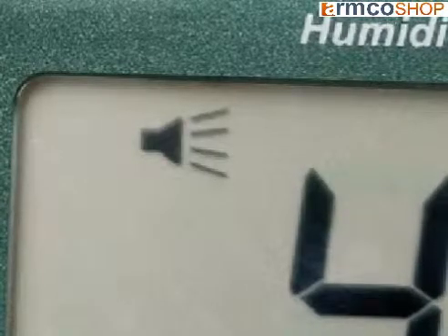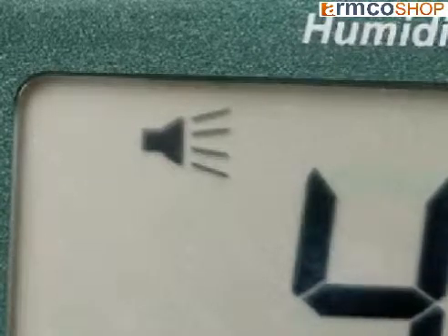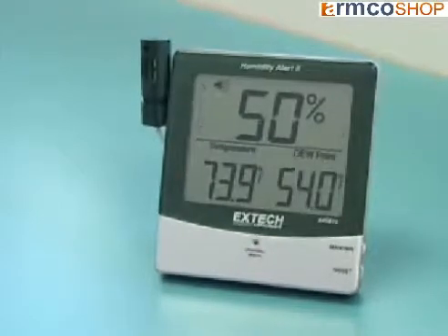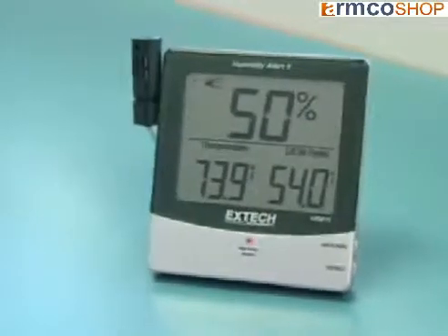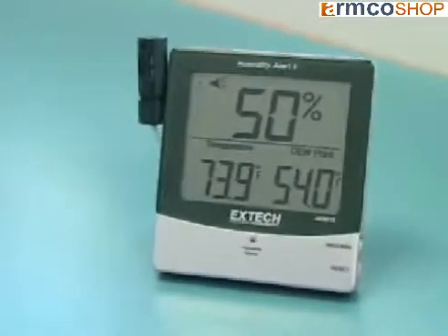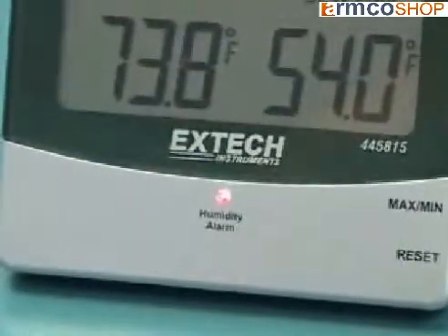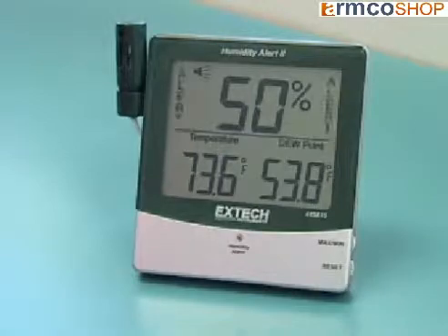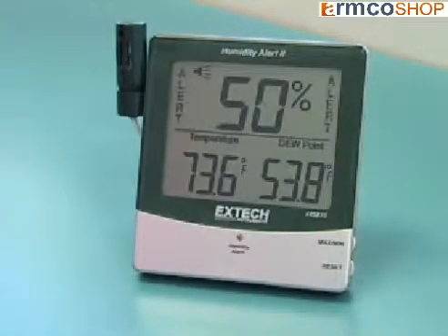Once activated, the alarm will trigger if the humidity level exceeds a preset high limit or a preset low limit. The alarm consists of a flashing light and audible beeper that will shut off automatically in 60 seconds. Alert warnings on the display will continue to flash until the humidity level goes below the high set point or above the low set point.